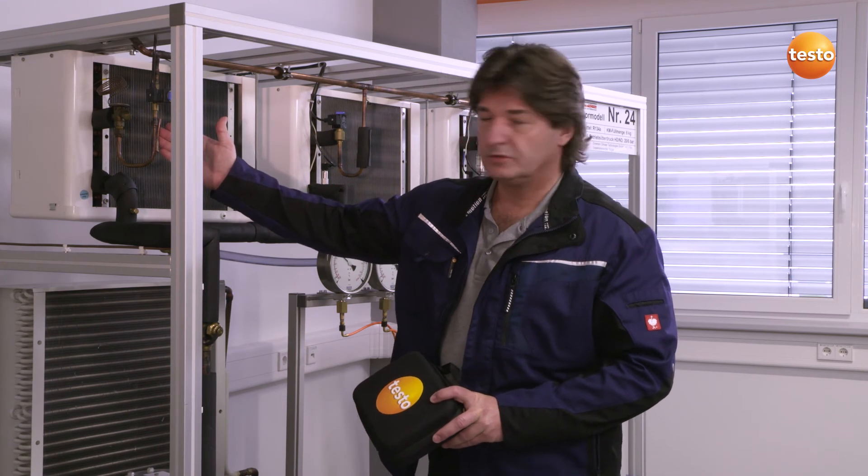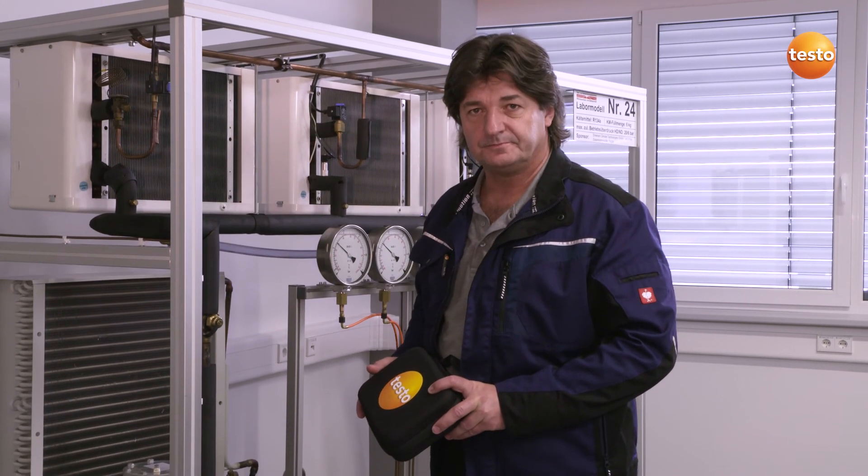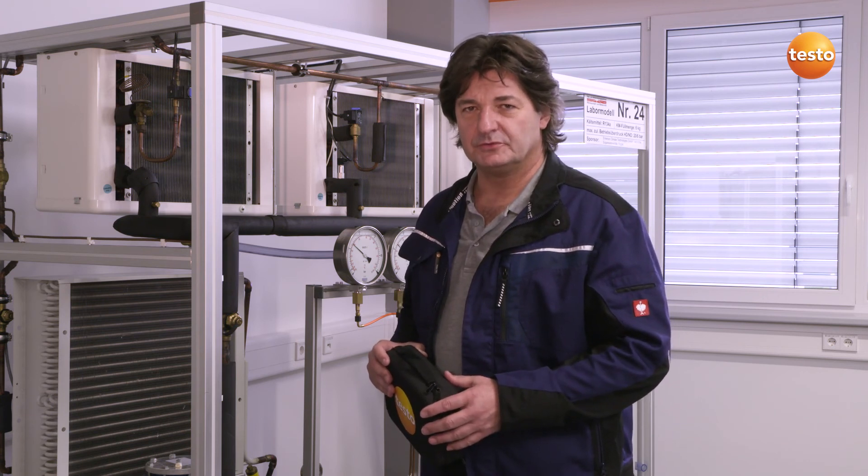The measurement shows me that in this case we have sufficient subcooling of the liquid before the expansion valve, but the evaporator superheating could maybe be improved a bit more. I'm really impressed with how quickly and accurately I've been able to take a measurement, create complete documentation on site, and send it as well. The stable radio links are extremely beneficial when the measuring points are far apart, for example in larger systems, meaning that measurement cables are unnecessary, as well as hose connections filled with refrigerants.